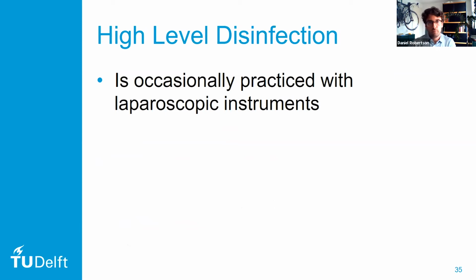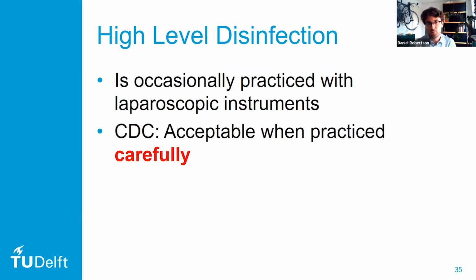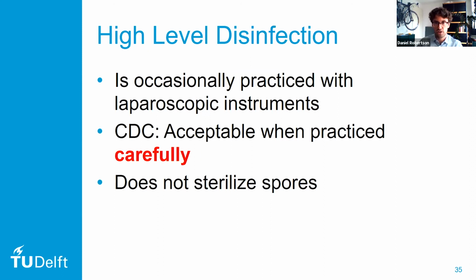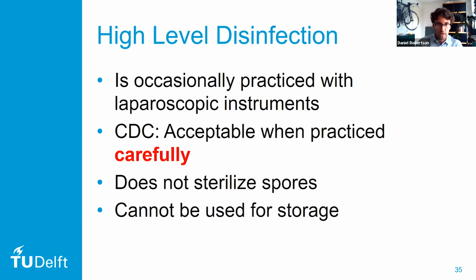Now, the other method that is very common, that we saw in the rural hospitals, is high-level disinfection. Now, high-level disinfection is occasionally practiced with laparoscopic instruments. And the CDC says that it's an acceptable method when practiced carefully. This careful practice of high-level disinfection makes it so difficult to safely execute, because there's a lot of points in high-level disinfection that can go wrong. And one other big drawback is that it does not sterilize spores. Also, one thing you have to take into account is that instruments that were disinfected by high-level disinfection cannot be stored afterwards, because you take the instrument out of generally a wet solution. It means that bacteria will immediately start to grow in the instrument, and you cannot store it.